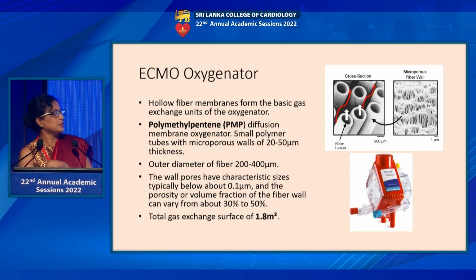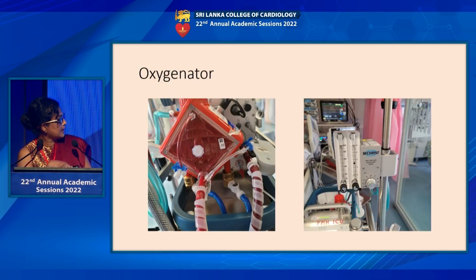So the next component is the oxygenator. The oxygenator is made up of a very thin material that is rolled up into tunnels like this, and inside the tunnels the gas will flow. Outside the tunnels the blood will flow, and the gas exchange will occur via diffusion. It's very efficient. In the CardioHelp machine, because of this structure, the total surface area is about 1.8 square meters. So this is how the oxygenator looks. This is the inflow, and this is the outflow. This is the gas supply, which is connected to the gas blender. And this is the warmer, the input connections of the warmer.